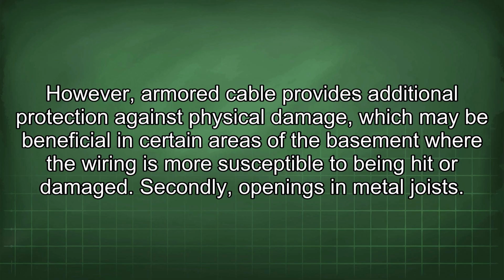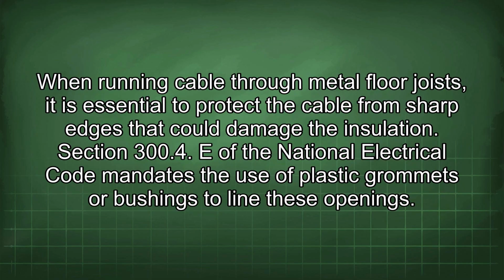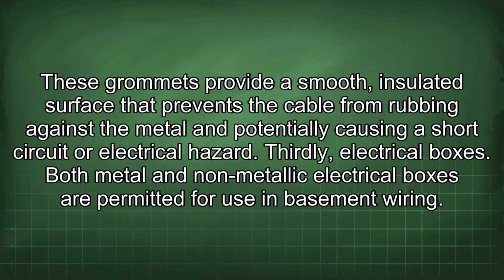Secondly, openings in metal joists. When running cable through metal floor joists, it is essential to protect the cable from sharp edges that could damage the insulation. Section 300.4 E of the National Electrical Code mandates the use of plastic grommets or bushings to line these openings. These grommets provide a smooth, insulated surface that prevents the cable from rubbing against the metal and potentially causing a short circuit or electrical hazard.